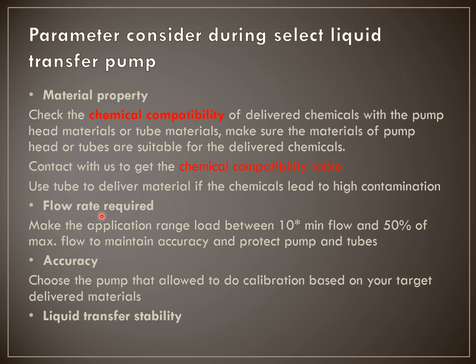The second parameter is flow rate. Based on our experience, we recommend your flow rate range be loaded between 10 times the minimum flow and 50% of the maximum flow. This considers not only accuracy but also the protection of the pump and the protection of the tubes.